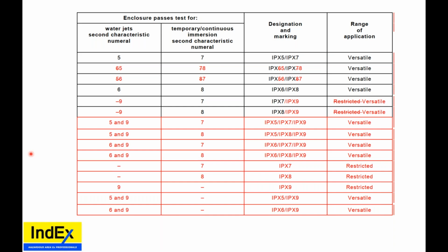Will all Ex certificates include the IP rating? I've seen some ATEX equipment that does not include the IP rating. Under the IEC standards, yes, they shall list the IP rating and shall have IP testing. If they don't, that's possibly going to cause the manufacturer to not be able to sell their equipment to certain end users, or procurement people will question their IP ratings.